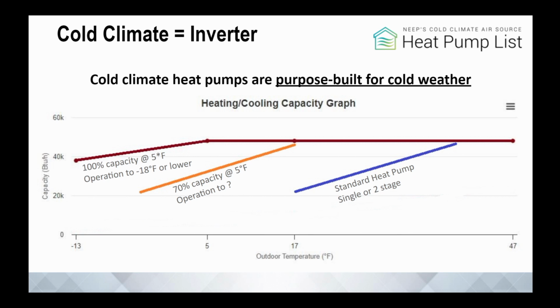What I want to point out is that orange line is sort of this next tier of heat pumps. They are cold climate according to definition, but still have a notable drop off starting around 17 degrees. We get colder than that pretty regularly in the Front Range and definitely up in the mountains. So my position is that category of equipment, while useful in maybe warmer climates, is not necessarily the right spec for the Front Range and the mountains.